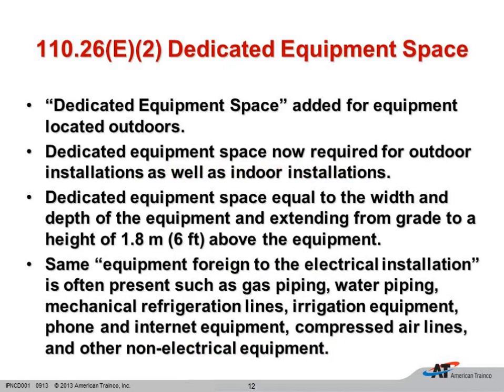This is a change in the general requirements of Article 110 for dedicated equipment space. Most of us have forever known that indoors, in front of our equipment, there are 3 conditions present, and we might have to have 3 feet, 3.5 or 4 feet depending on the condition we're facing. So now this has been expanded to outdoors. I don't know how many of you might be contractors or associated with putting in services, but the service entrance outdoors can sometimes get a little messy with these other systems. I've seen everybody want to come near our service entrance, whether it's the gas piping or all the communication equipment or whatever it might be.